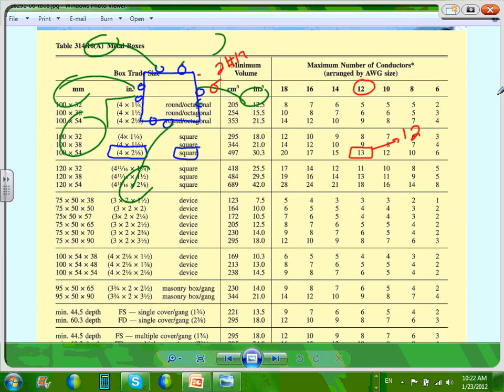Does that make sense? When you guys, especially when you're doing the takeoff for a project, you put a box limited to 4 fixtures coming out of it, you're good to go. You don't exceed. Otherwise, what happens if you exceed? You're getting into bigger boxes. If I want to go to the deepest, biggest square box that I can use as a J box, I can go all the way up to 18. Typically, you limit yourself to 4 and you work with them. But if you want the bigger boxes, you can. If you are in this situation, you have another option, but no more than 18 though.